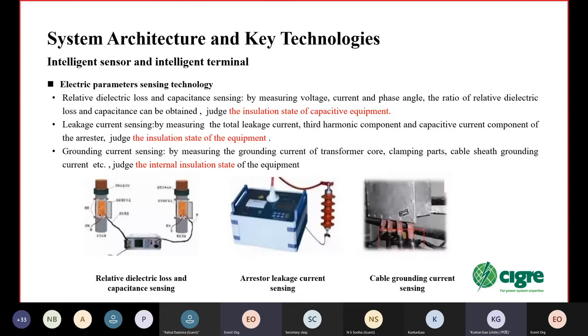The most important type of sensor is the electric parameter sensor. Relative dielectric loss and capacitance sensing: by measuring voltage, current, and the phase, the ratio of the relative dielectric loss and the capacitance can be obtained. It is used to judge the insulation state of the equipment.